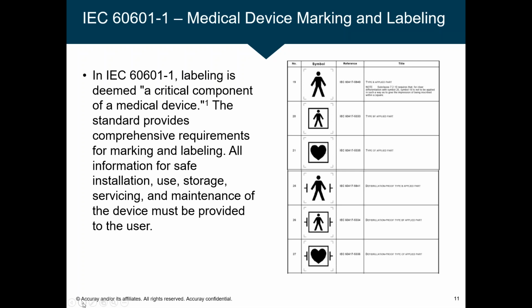And usually the way that you resolve something like that when you have conflicting requirements is I bring in systems engineering, and I bring in regulatory to help determine that. You know, you always can put both. So we actually put both of these symbols on our labels and in our symbol stock, because that way you're covered.